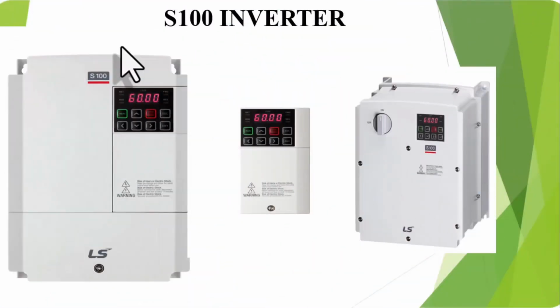Hello friends, continuing with the instructional videos on the S100 inverter from the LS brand. In previous videos we covered how to start and stop from the keypad, set the frequency from the keypad, set the frequency via analog voltage input 0 to 10 volts, and set the frequency via analog current input 4 to 20 milliamps. Today we want to set the frequency for the S100 inverter via the network and also perform start and stop through the network.